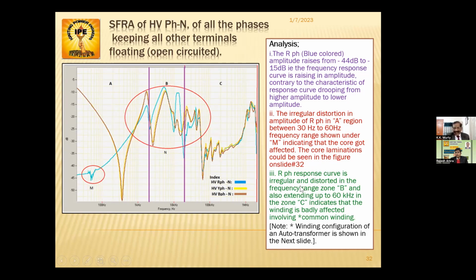And R phase response curve is irregular and distorted in the frequency range zone B, and also extending up to 60 kilohertz in this zone C, indicates that winding is badly affected, involving common winding. So here you can see this blue here. So this point is 60 kilohertz. See, this is 100 kilohertz. So this is 60 kilohertz up to here. So this is this ellipse what I have drawn in B this thing area region.